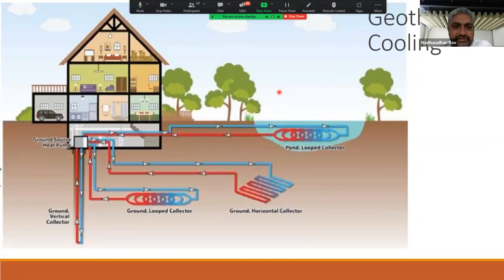Second is our soil temperatures are much higher than Western Europe or Northern America. Generally, the rule of thumb says that whatever is the average ambient temperature of that location, let's say Delhi, that would be the normal ground temperature, uniform throughout the year. So obviously, Delhi's annual average temperature is higher than Paris, higher than Munich. So your ability to reject heat to the ground is affected, because whether you're in Paris or in Delhi, your condenser water outlet temperature will be 35 degrees or 32 degrees, right?